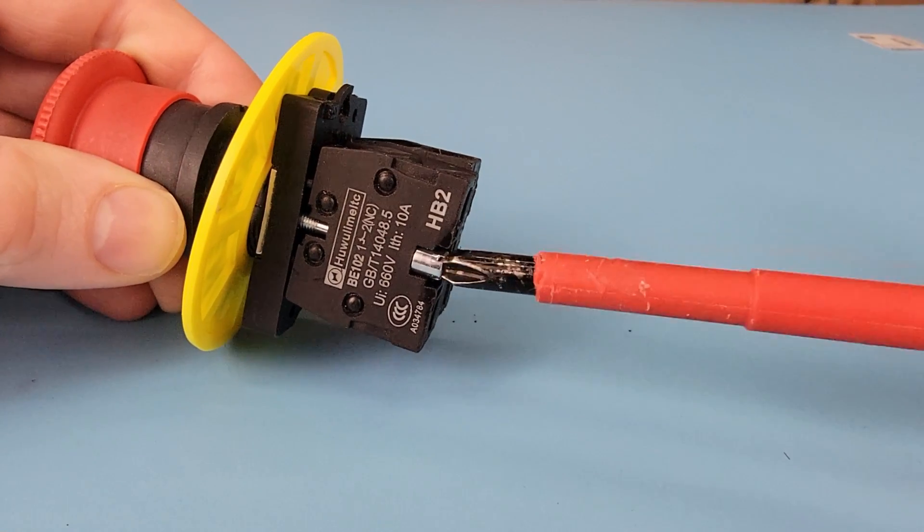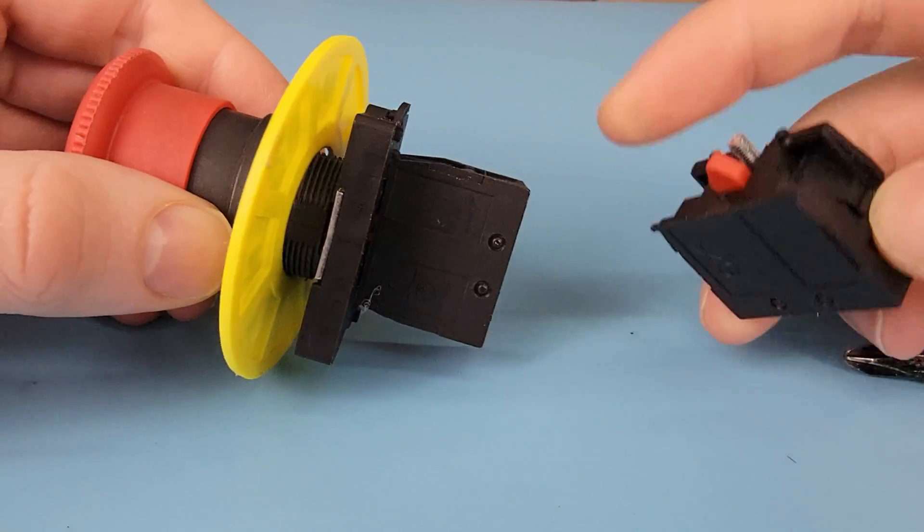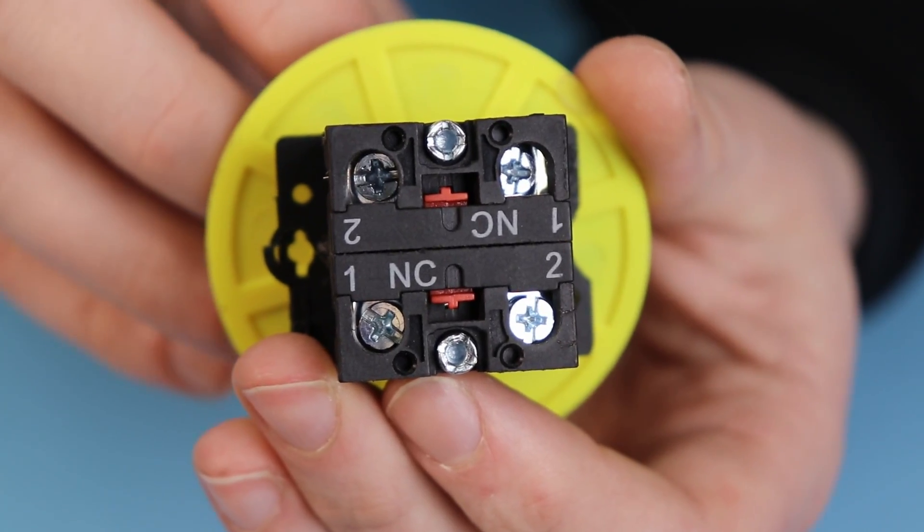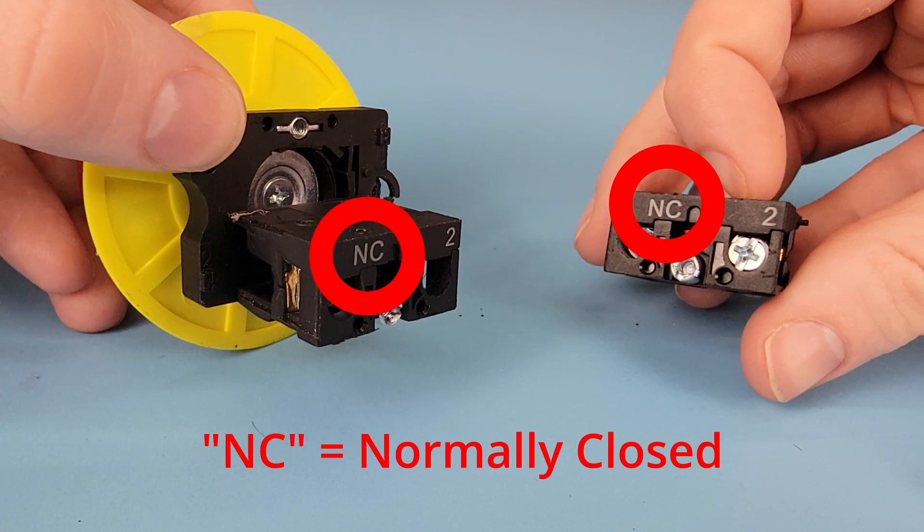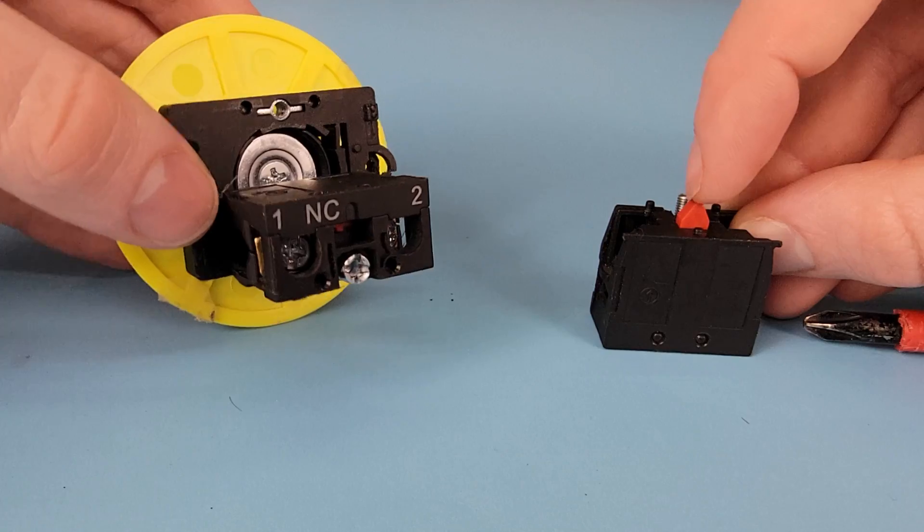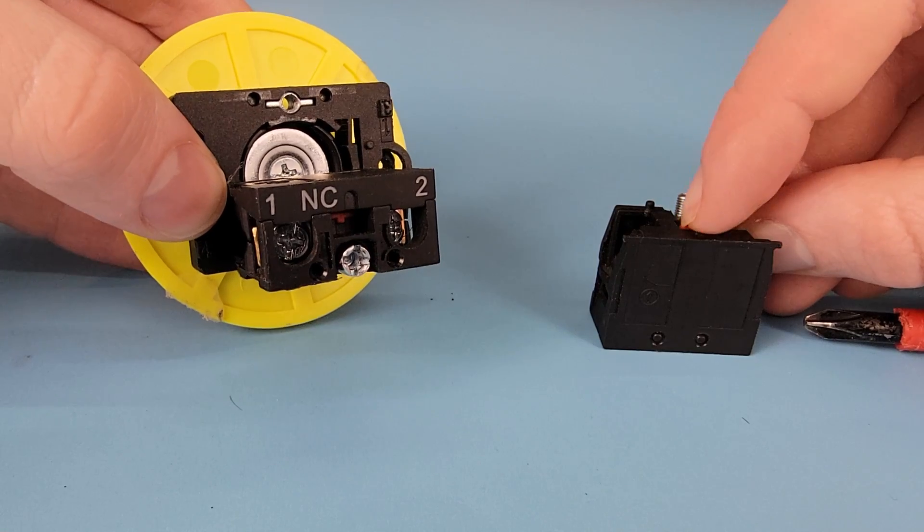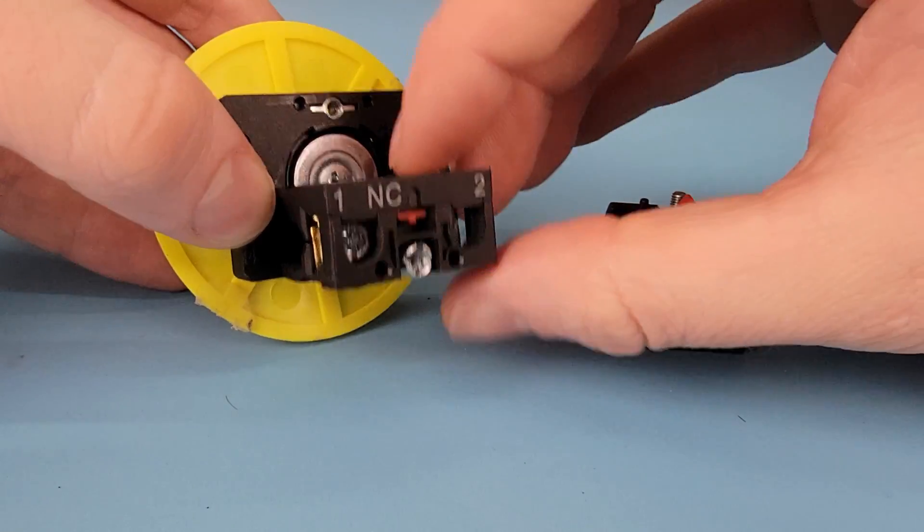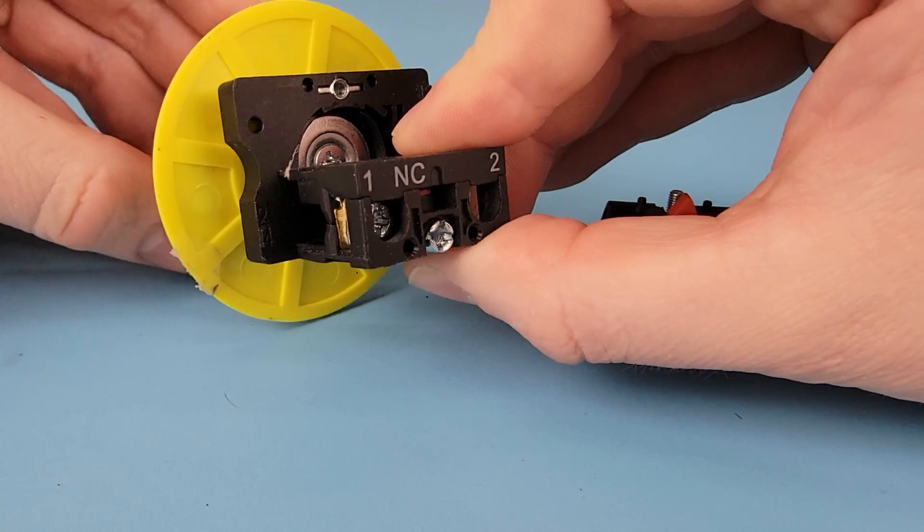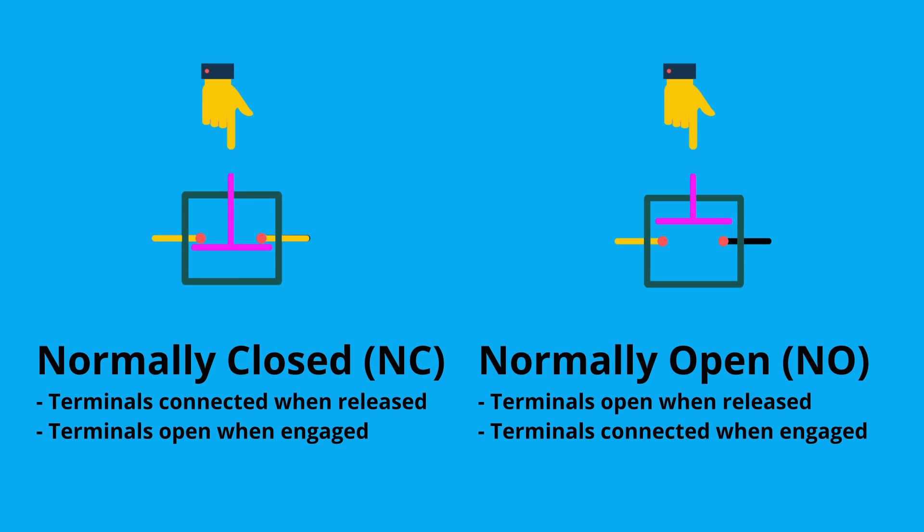Generally speaking, the emergency stop button comes with two switches. You'll see both these pieces on mine say NC, meaning they're normally closed switches. These two screw terminals are normally connected, but then when the emergency stop button is pressed, they open up. You can also buy normally open emergency stop buttons, which act in the inverse. Normally the switch is open and closed when the emergency stop button is engaged.